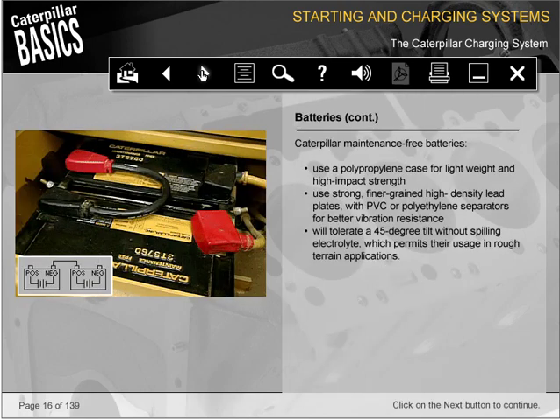Caterpillar maintenance-free batteries use a polypropylene case for lightweight and high-impact strength. They use strong, finer-grained, high-density lead plates with PVC or polyethylene separators for better vibration resistance. They will tolerate a 45-degree tilt without spilling electrolyte, which permits their usage in rough terrain applications.